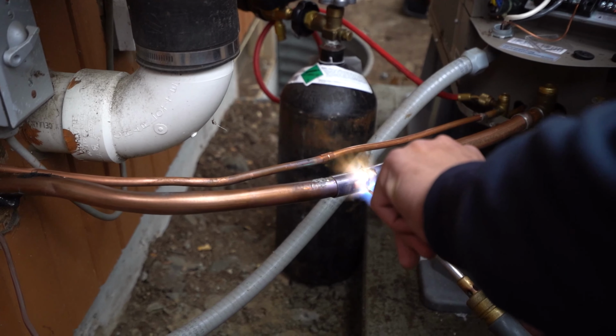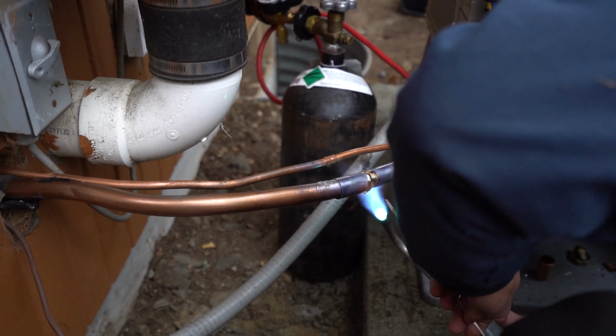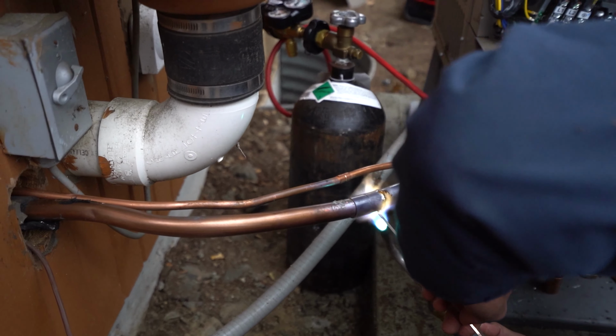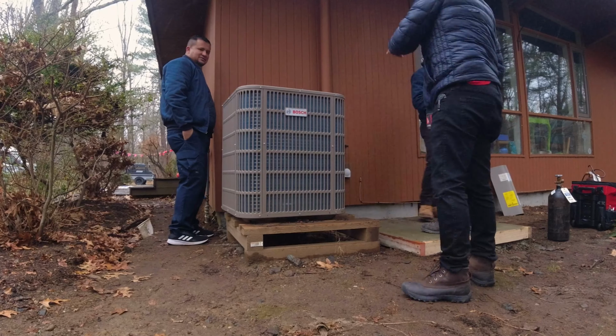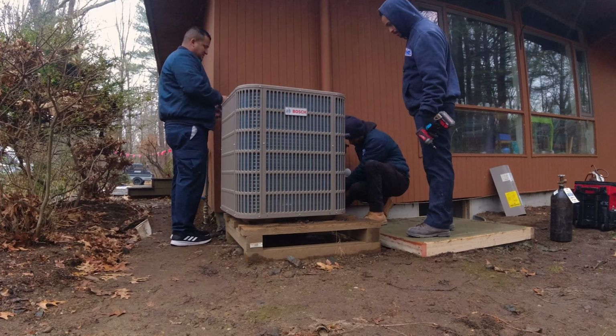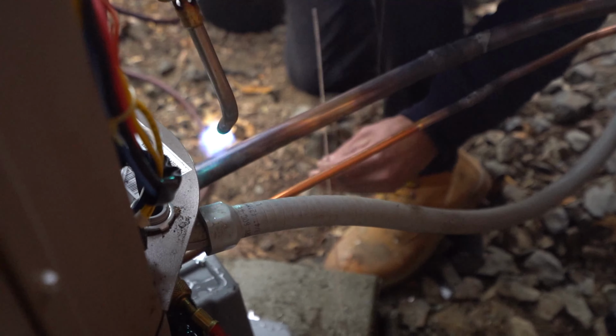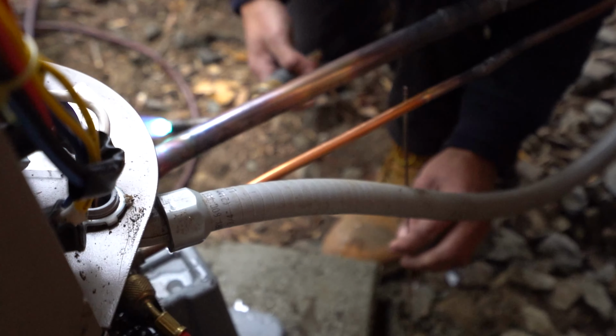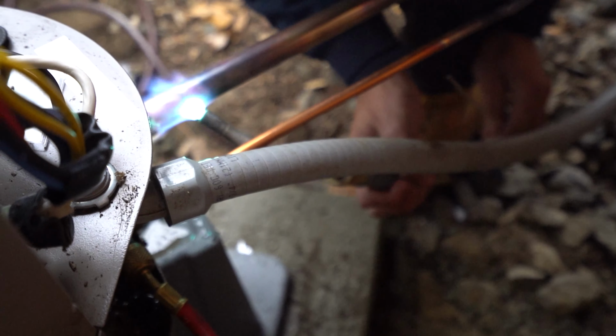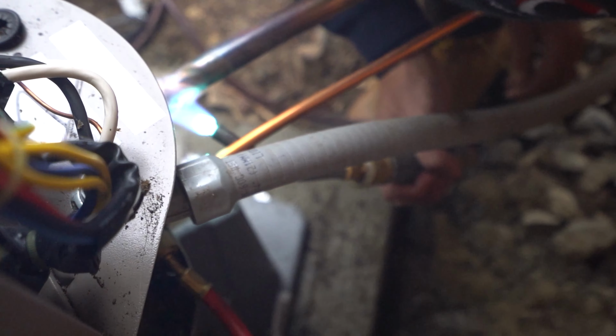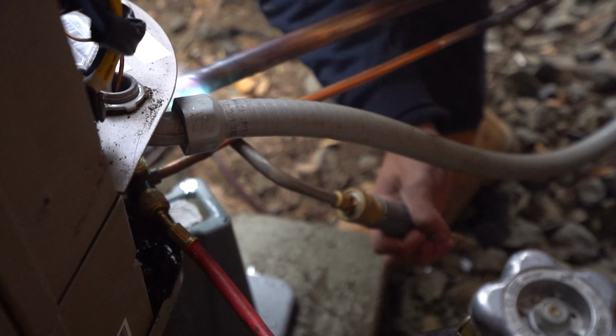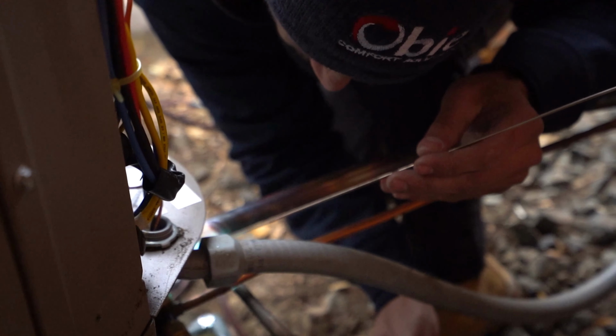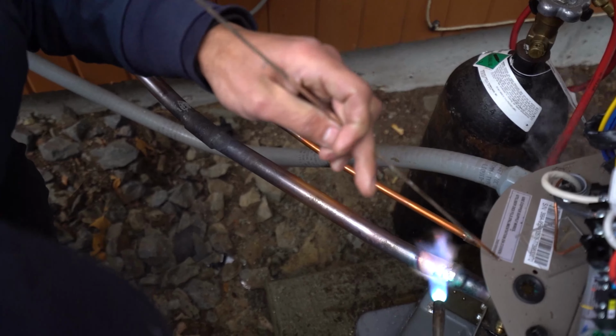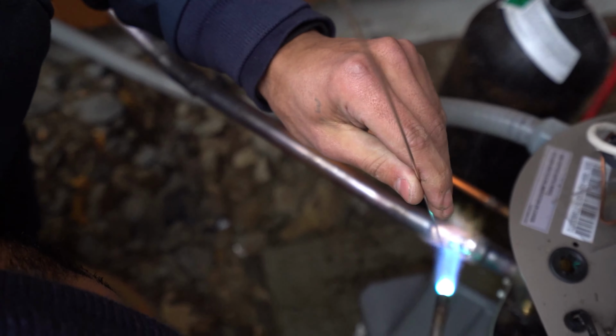Even if this was done properly and if it was holding, it's not the proper solder. The R410A is a high pressure refrigerant and requires the silver brazing alloy, which is a different solder. It's just more resistant and is made for refrigeration. Contrary to what they used here, which is made for plumbing, for water, and it's a completely different application.